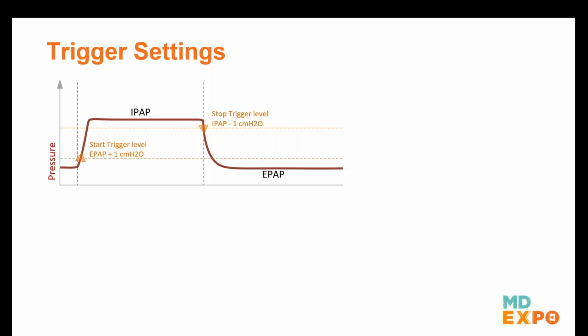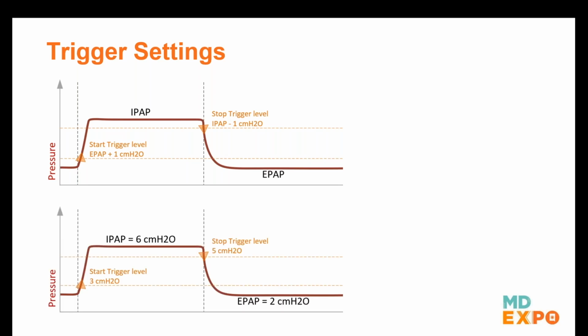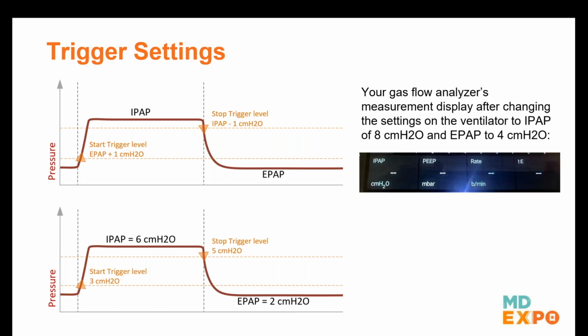But the challenge here is that these trigger levels are dependent on the settings of my ventilator. Let's assume that the first setting I have to test is an IPAP of 6 and an EPAP of 2. I would then set my start trigger to, let's say, 3 centimeters of water pressure and my stop trigger to 5. And let's assume that my next setting on my ventilator is an IPAP of 8 and an EPAP of 4. As soon as I apply these settings, my gas flow analyzer is going to go, whoop, and not measure any breath-based parameters anymore. Why is that?